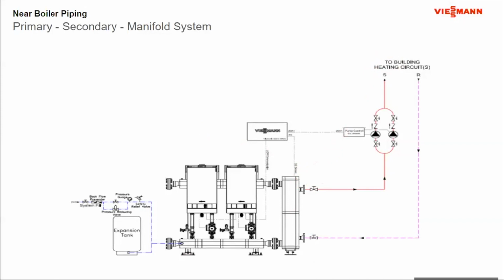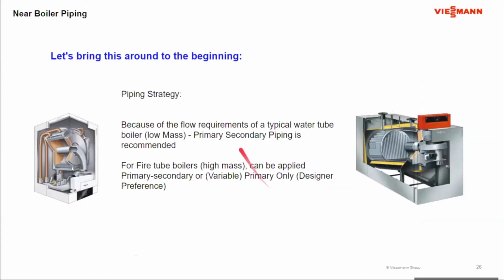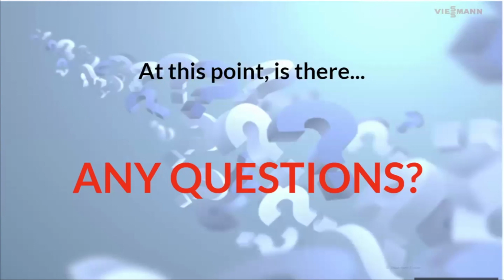And then when we start to look at the variable primary, the primary only, now we're typically looking at fire tube boilers, your floor standing larger mass boilers. Again, in summary, primary, secondary is required or recommended when I do wall hung boilers, low mass water tube boilers. But when I do floor standing fire tube boilers, typically there's a large mass in there, and these can be applied either primary, secondary, or variable primary. So covered a bit of ground at this point, so I think it's a good place to stop and see if there's any questions.